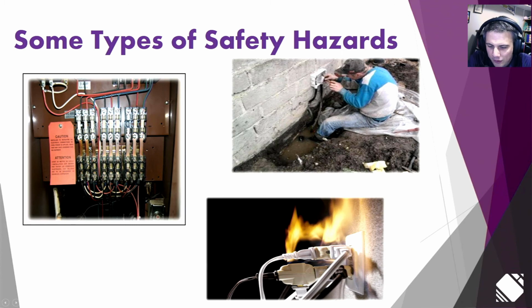Perfect. Looking at this picture, you can see a tag explaining that during shipment, components could become loose and need to be investigated by trained personnel to make sure the fuses and everything else are tightened to manufacturer specifications. If anything did come loose, you can get small arcing inside the connection, and over time that small arcing creates heat and damage, leading to large arcing, which is a safety issue.